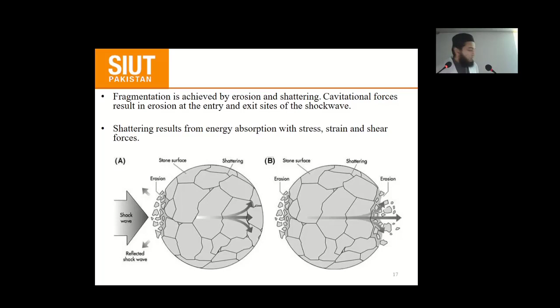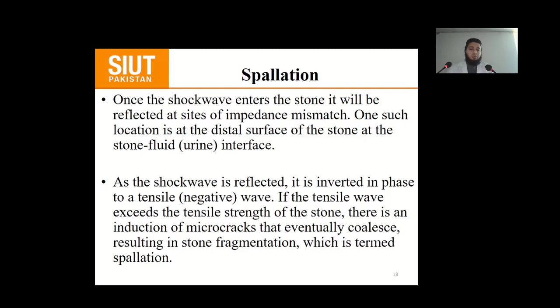So what is spallation? Once the shock wave enters the stone, it will be reflected at sites of impedance mismatch. One such location is at the distal surface of the stone at the stone-fluid interface. As the shock wave is reflected, it is inverted in phase to a tensile negative wave. If the tensile wave exceeds the tensile strength of the stone, there is an induction of micro cracks that eventually coalesce, resulting in stone fragmentation, which is termed spallation.